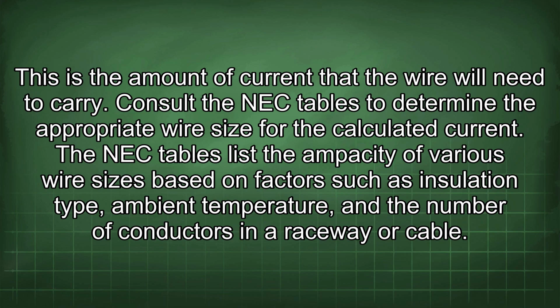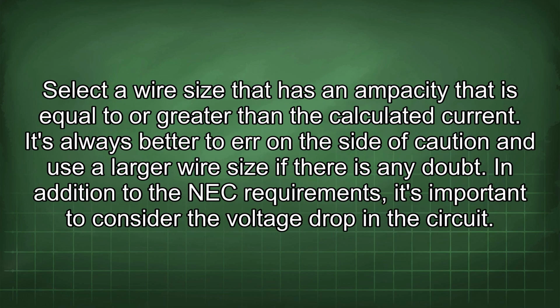Consult the NEC tables to determine the appropriate wire size for the calculated current. The NEC tables list the ampacity of various wire sizes based on factors such as insulation type, ambient temperature, and the number of conductors in a raceway or cable. Select a wire size that has an ampacity that is equal to or greater than the calculated current. It's always better to err on the side of caution and use a larger wire size if there is any doubt. In addition to the NEC requirements, it's important to consider the voltage drop in the circuit.